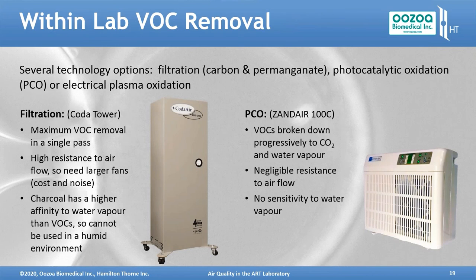Within the lab, you can remove VOCs by a range of technologies: filtration using carbon and permanganate filters, or photocatalytic oxidation, so PCO, or electrical plasma oxidation. So the two most common systems are the filtration ones, like the Coda Tower. It has a maximum VOC removal per pass, but its filters give it a high resistance to airflow, so you need larger fans, which makes it more expensive to buy, to run, and noisier. The other thing to remember is that charcoal has a higher affinity to water vapor than it does to VOCs. So if you use this in a humid environment, it will not work as you think.